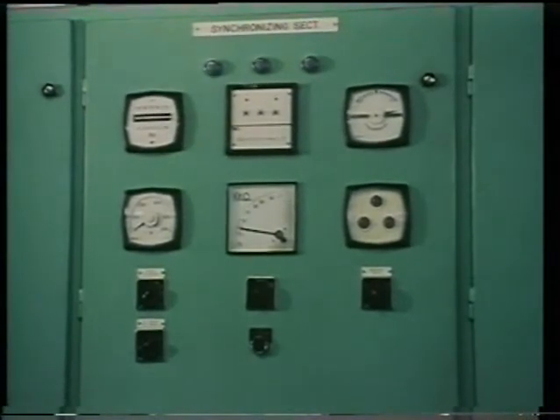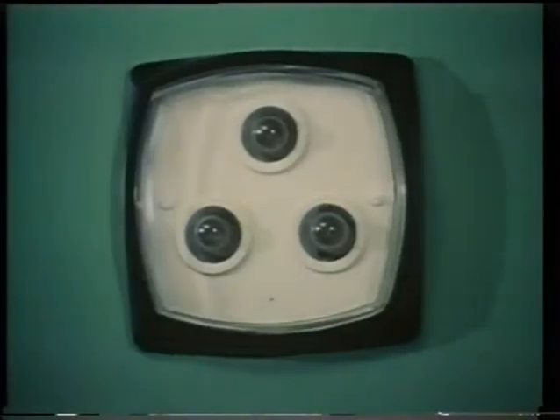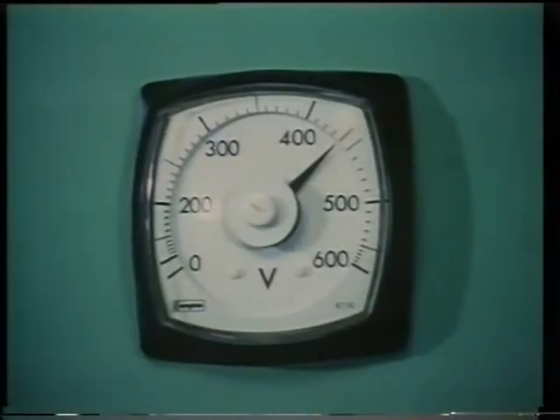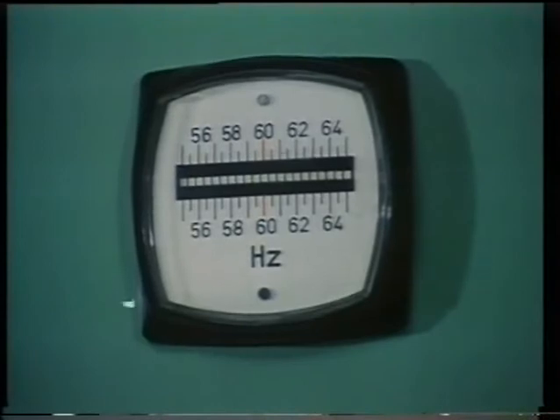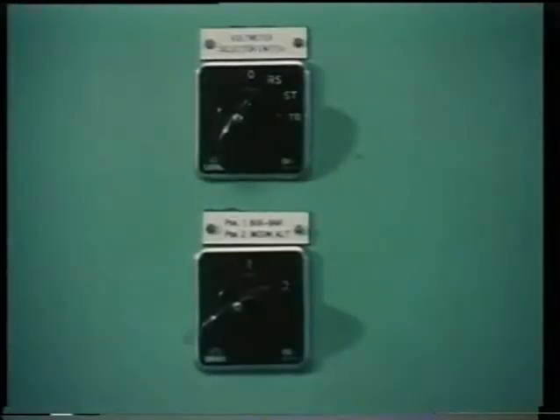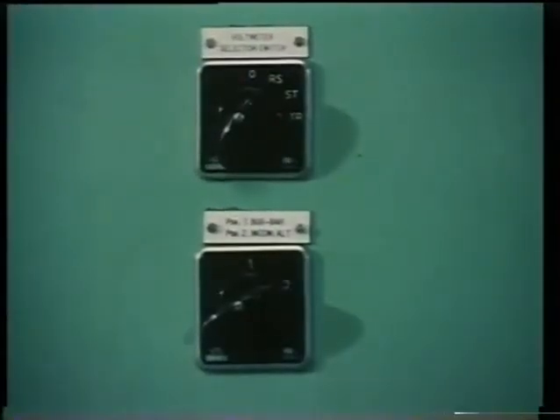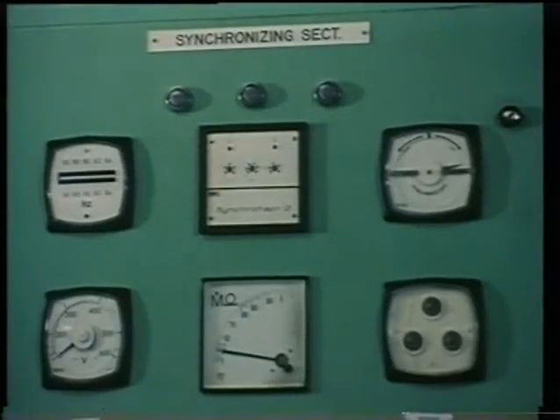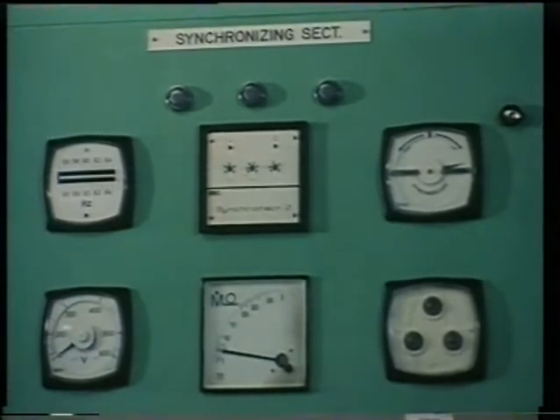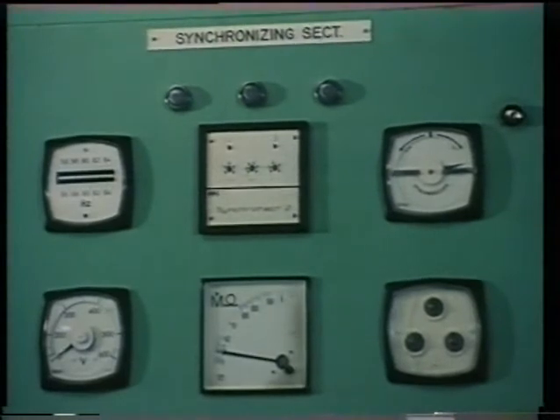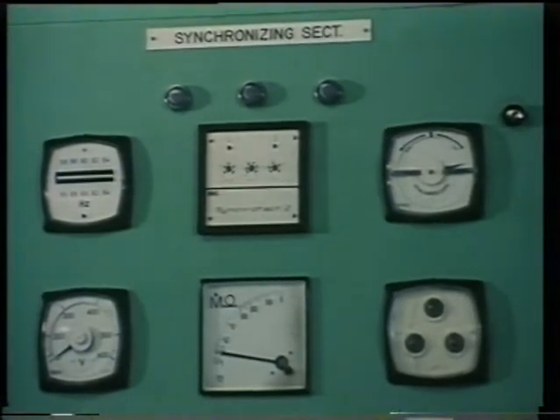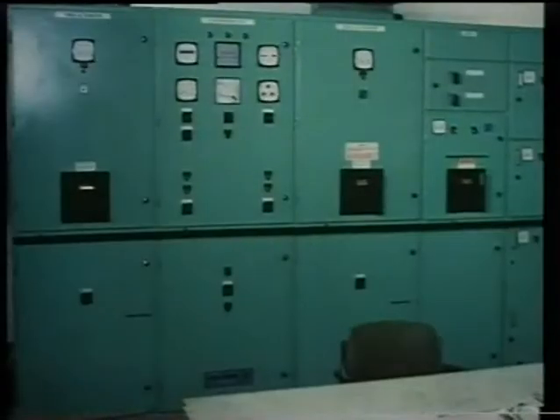These may be either a synchroscope or synchronizing lamps, or both. In addition, the panel has voltmeters and frequency indicators. Changeover switches determine whether the meters show the incoming data or the output of the unit supplying power to the bus bars. All these instruments are usually duplicated on the main control console for remote operation. A detailed description of manual synchronizing is given in Programme 3.